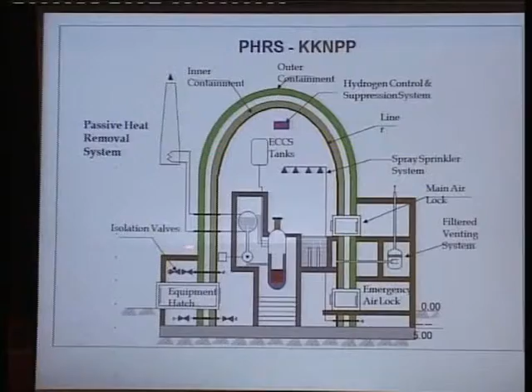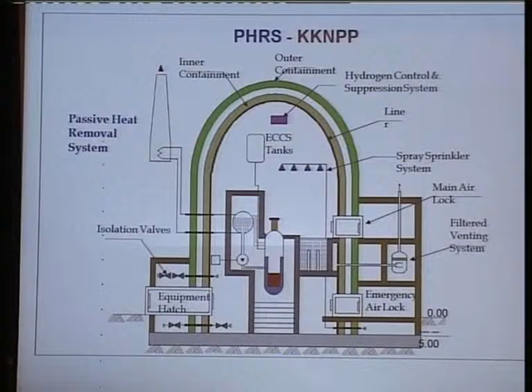Then we have another very interesting feature: located on the outside of this outer containment is a whole lot of radiators, rather like motor car radiators, where the secondary side water can be cooled by air. These are fin tube heat exchangers—a tube with a lot of fin surface that, just by exposure to air, is able to transfer the heat.